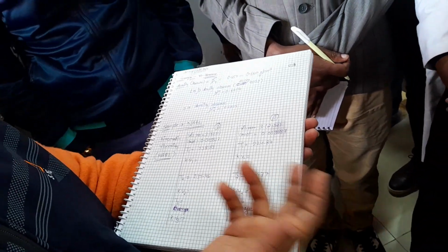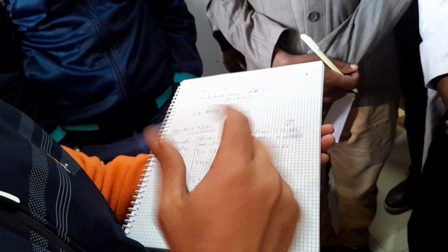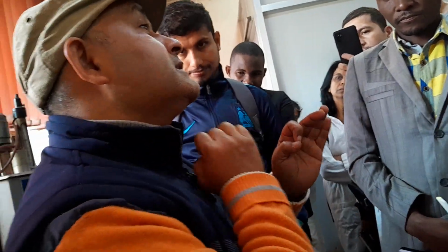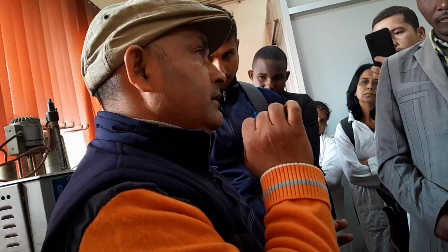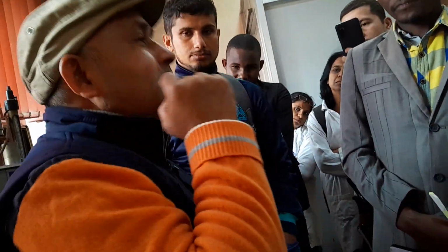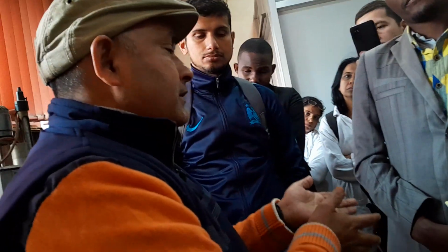Otherwise, first you take one viscometer, and if it takes more time, there will be a confusion. What confusion? The capillary is very fine. One confusion is that there may be choking inside the capillary, which is not visible, and the time is higher. You are thinking that okay, my time is maximum, my result will be good, but there is a choking inside the capillary, and that is why the time has been more. So the minimum time is 200 seconds, and a maximum of 1000 seconds is sufficient.